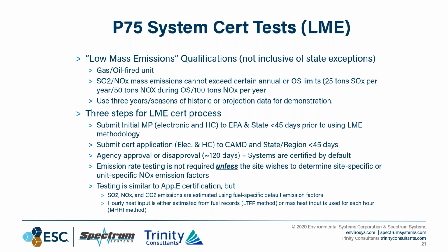And your hourly heat input can be either estimated from your fuel records using a long-term fuel flow method over the course of operation, or a maximum heat input value is used for each hour. I've seen it go both ways on this, and you get a lot closer to accuracy using a longer term fuel flow method than you do with maximum heat input. When they say max heat input, that means every hour is the maximum heat that you can output from the unit. Long-term fuel flow, you wind up having to go back and apportion fuel use for each hour.